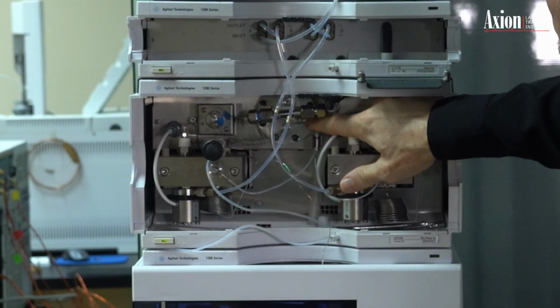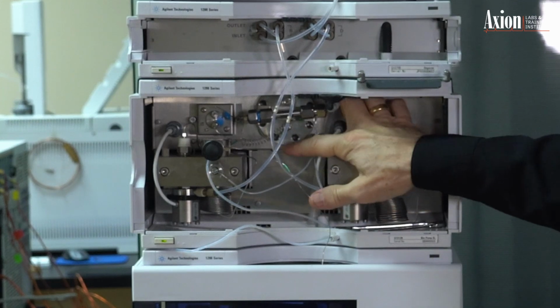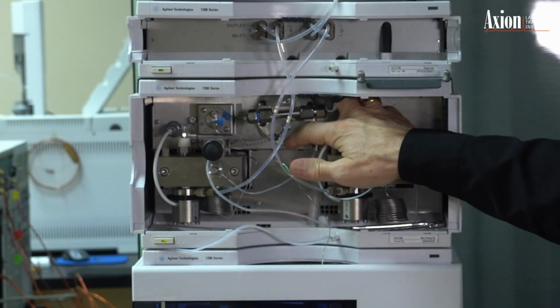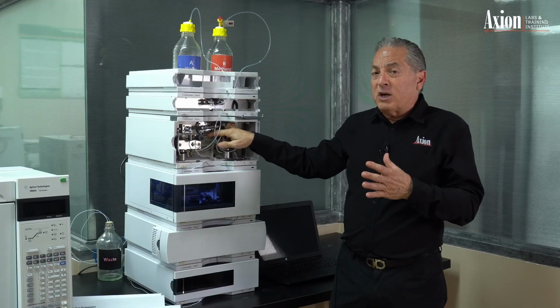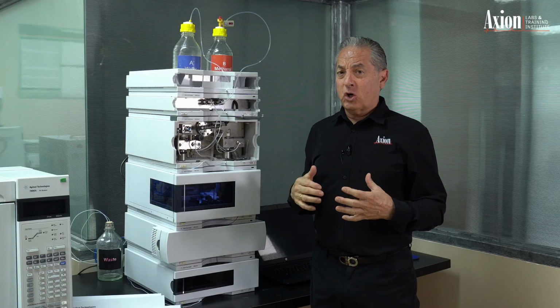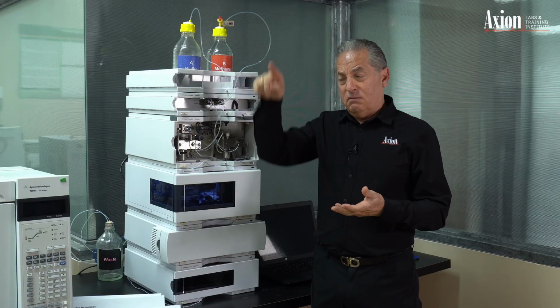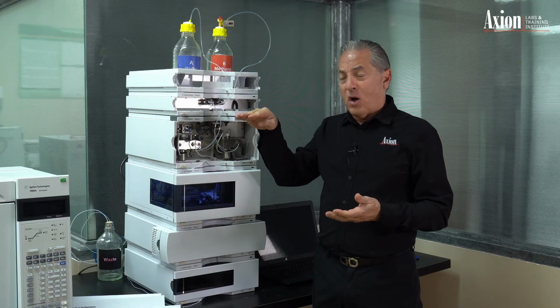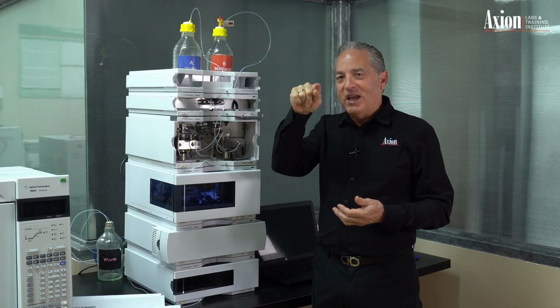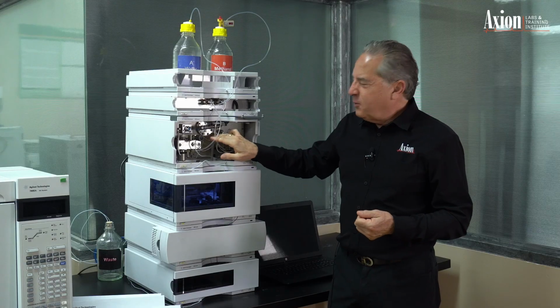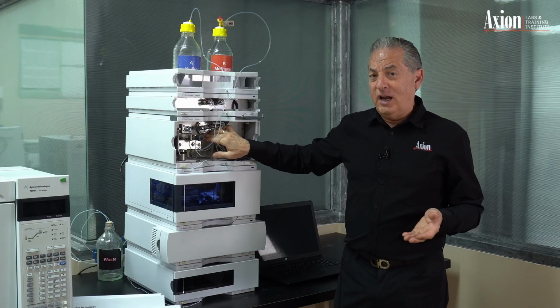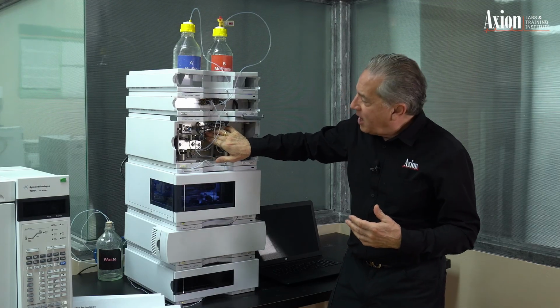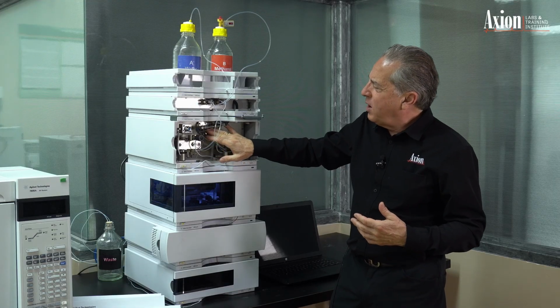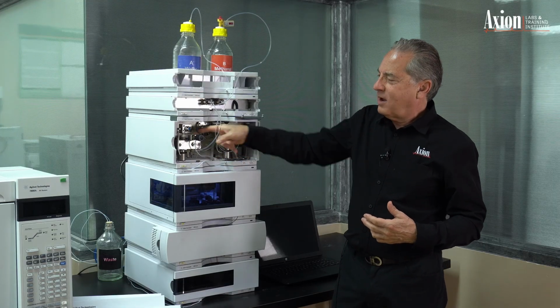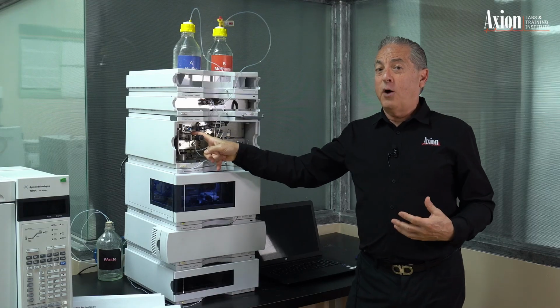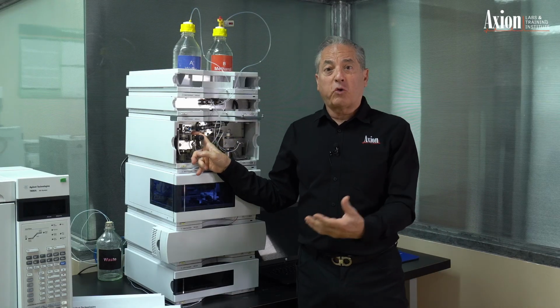So the pulse dampener is this thing that's sometimes called a hockey puck. It's just round and flat like a hockey puck. It is filled with a compressible liquid, like a nitrogen shock absorber on your car. And again, it's going to take the big pulsations and make them smaller. In this case, it's going to take the small pulsations and make them even tinier. I think we get like a 98% reduction in the pulsation going through there. So we go in the hockey puck, we come back out, and at this point, the tubing goes to the back of this purge valve, and we are now ready to start the chromatography.